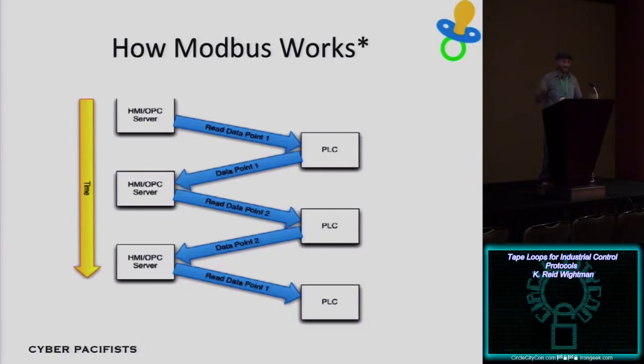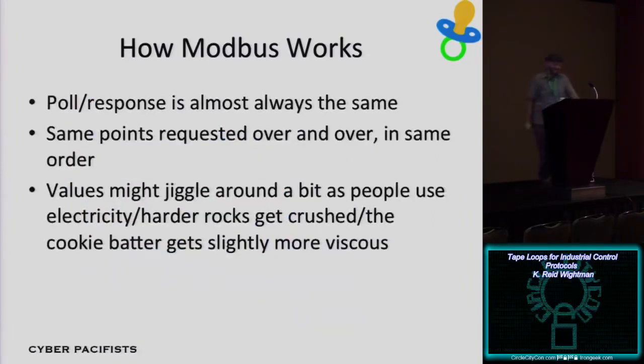So Modbus isn't really what you would call a real-time control protocol. You're getting these two discrete pieces of information, and they're slightly time separated. So if the heater element flicked on and off really quick, you wouldn't actually see it on your HMI screen. It's not super important, but it's something to think about when playing with control systems protocols. How Modbus works is, these polling sequences are almost always the same. It's always asking for the same pieces of information from the PLC in exactly the same order. Hey, what's the status of the heater now? What's the temperature now? What's the status of the heater now? What's the temperature now? And it just keeps doing that.